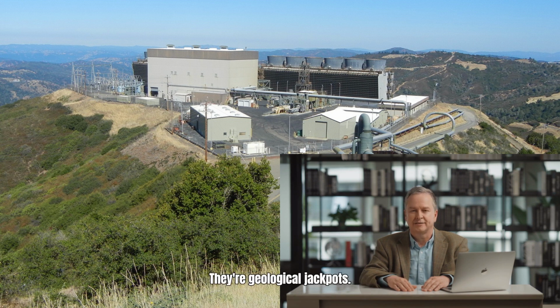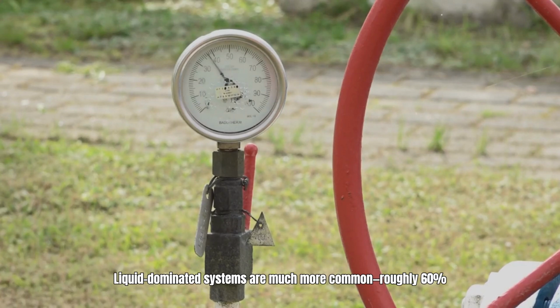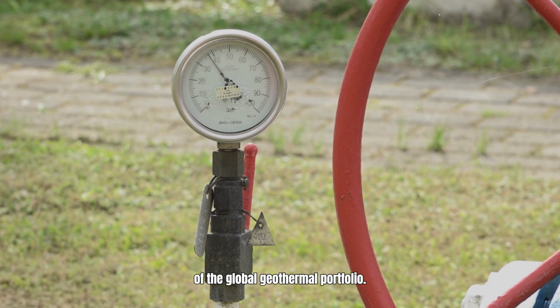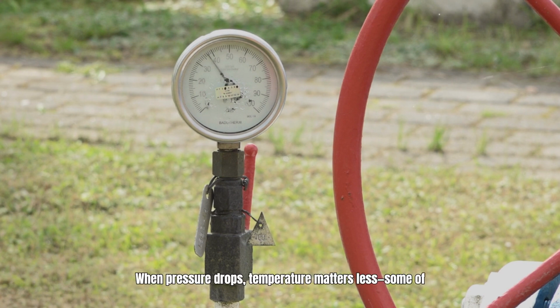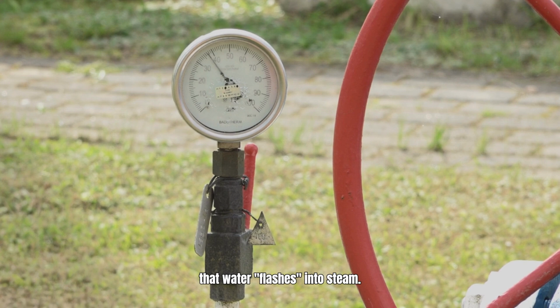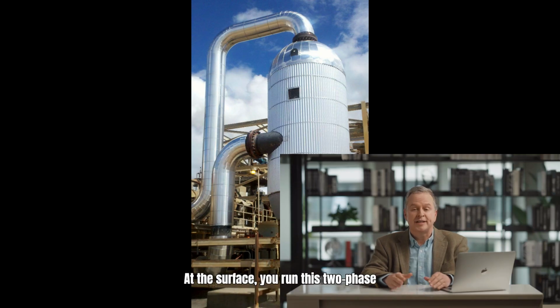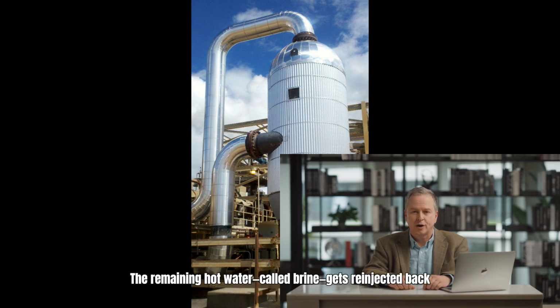They're geological jackpots. Liquid-dominated systems are much more common, roughly 60% of the global geothermal portfolio. Here, the reservoir contains superheated water under immense pressure. As this water travels up the wellbore toward the surface, the pressure drops, and some of that water flashes into steam. At the surface, you run this two-phase mixture through a separator. Steam goes to the turbine to generate electricity. The remaining hot water, called brine, gets re-injected back into the reservoir to maintain pressure and sustainability. This is called a flash steam plant, and it can be single flash or double flash depending on how many times you separate the fluids.